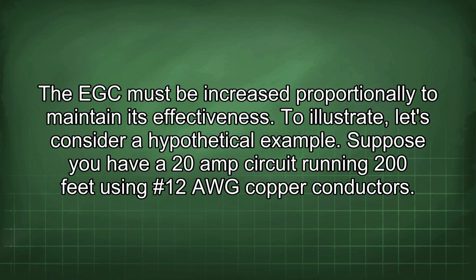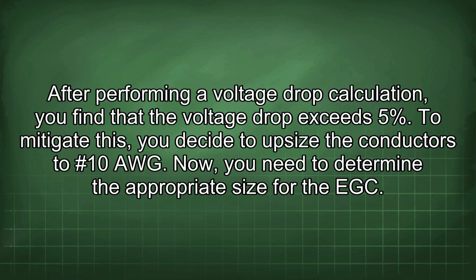To illustrate, let's consider a hypothetical example. Suppose you have a 20 amp circuit running 200 feet using #12 AWG copper conductors. After performing a voltage drop calculation, you find that the voltage drop exceeds 5%. To mitigate this, you decide to upsize the conductors to #10 AWG. Now, you need to determine the appropriate size for the EGC.